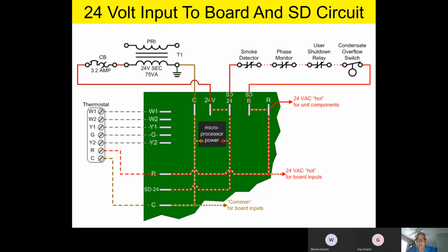Now, as you take a look at this little block diagram, from the 24 V portion over to SD24 and SDR, that's your smoke detector circuit. Now, fellas, it should be noted from the factory, if you do not have a factory installed smoke detector, phase monitor, or other sort of shutdown system, what you're going to have between SD24 and SDR is just a red jumper, and it typically sticks out about 1 inch. And it's very, very distinct. It's just a red jumper that goes between SD24 and SDR.